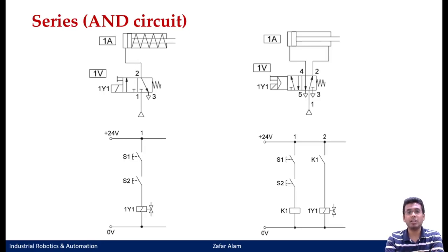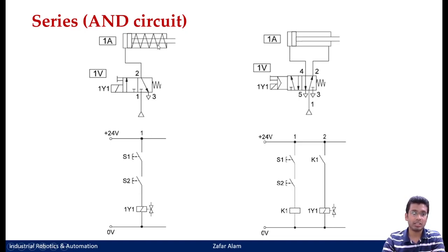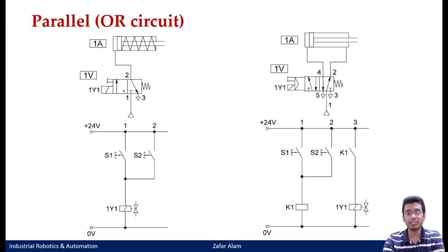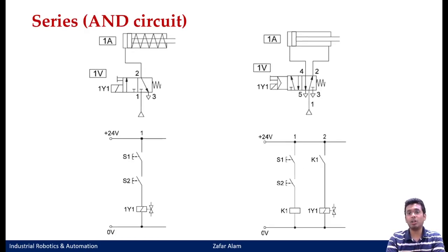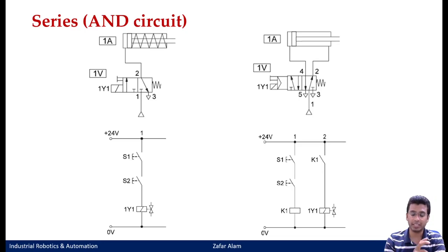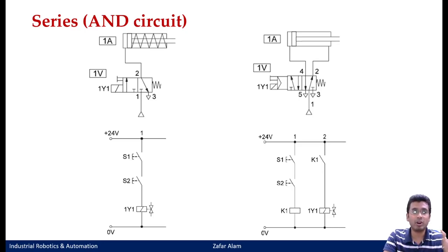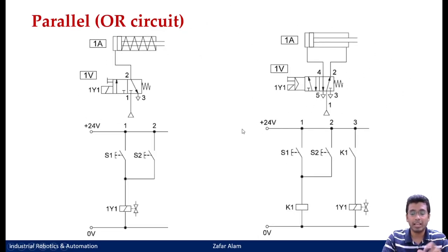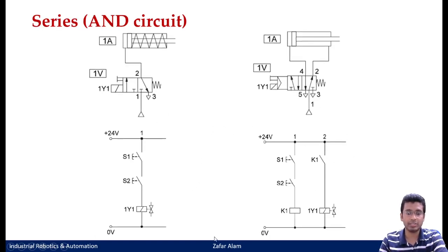This is a parallel circuit for OR logic. Similarly, you have your series circuit for AND logic — you just have to connect push buttons in series to actuate the AND logic in case of an electro-pneumatic circuit. Even if you see your pneumatic circuit diagram for both OR and AND circuits, they both remain the same — there is no change to it. The changes are only in the electrical circuit, because all your logic processing is done in the electrical portion. Your pneumatic portion does not have any control elements in case of an electro-pneumatic circuit. So in both single acting and double acting cylinders executing OR or AND logic, the pneumatic section is the same, and the only changes are in your electrical sections.